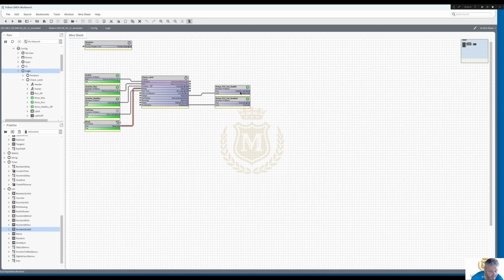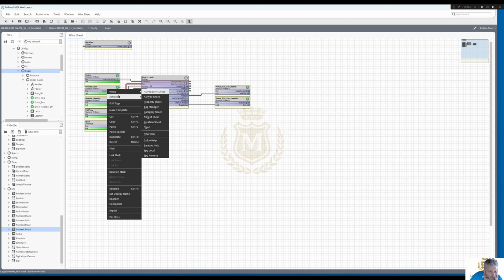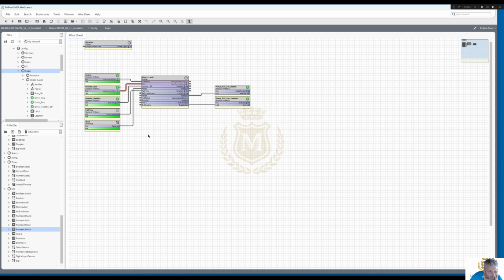So reset a block. We've got healthy, we've got true, so it's counting down now. We need to get this inverter run signal or the DP or the flow switch, whatever you want to call it, we need to get that into a true state before 30 seconds is up. Now it's true, the countdown has stopped counting down, and that will carry on running with no issue whatsoever.